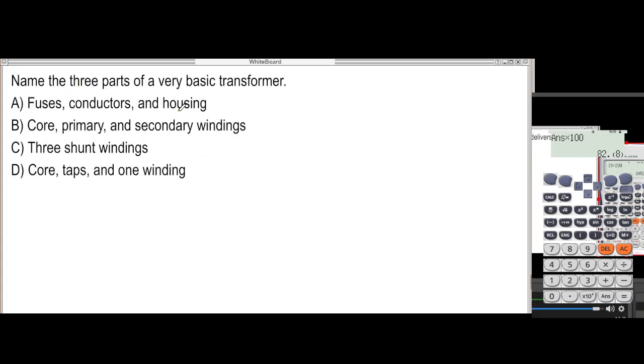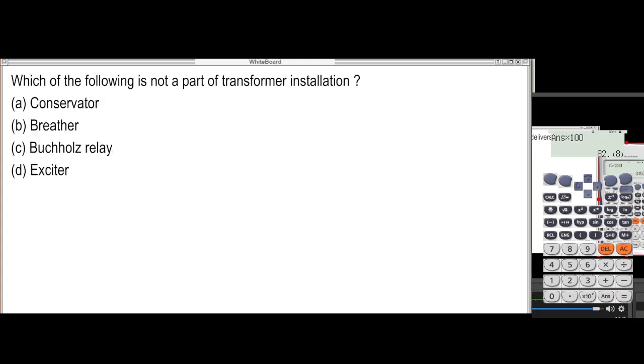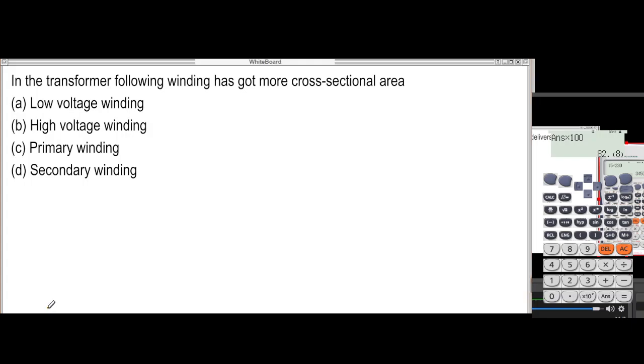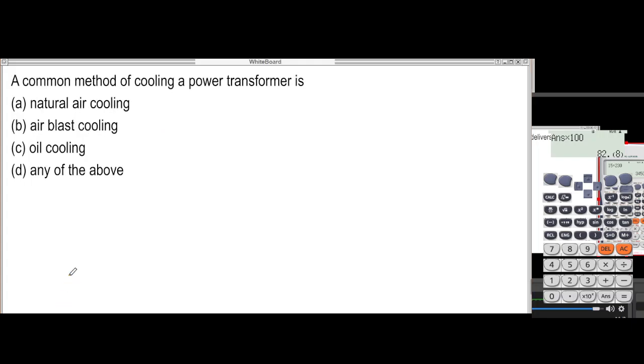Name the three parts of a basic transformer: that will be our core, primary, and secondary winding. Which of the following is not part of a transformer? The exciter. There is no exciter in our transformer. In the transformer, which winding has more cross-sectional area? Its winding is a bit bigger, so that will be the high voltage winding. A common method of cooling a power transformer is any of the above. It can be oil cooling, air blast, or natural air.